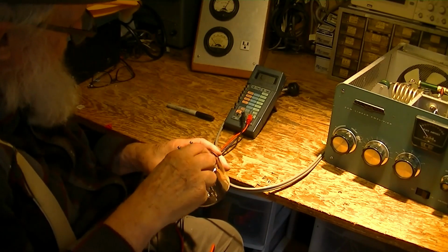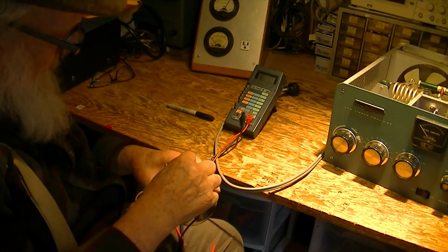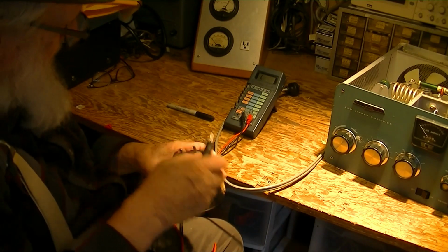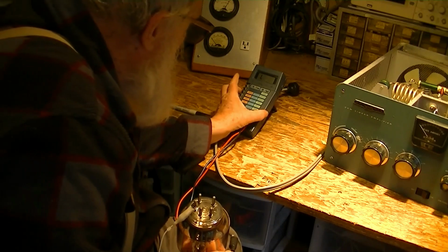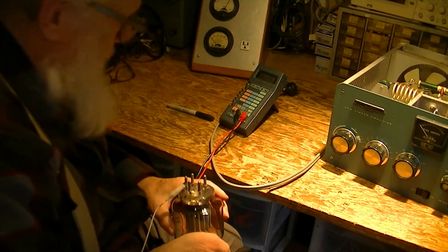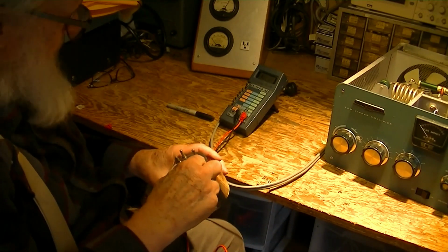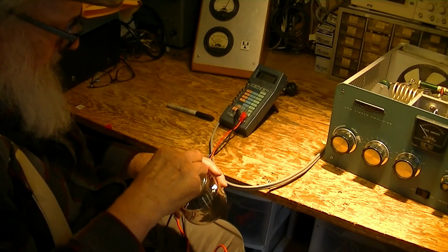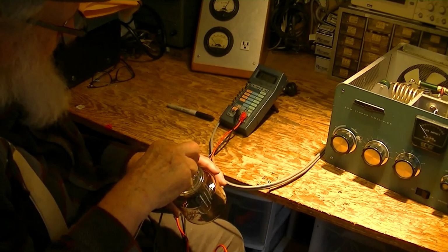Then I'm going to test for a short between the filament and the grid. I'm going to go all the way up to 20 megs. No short between the filament and the grid.